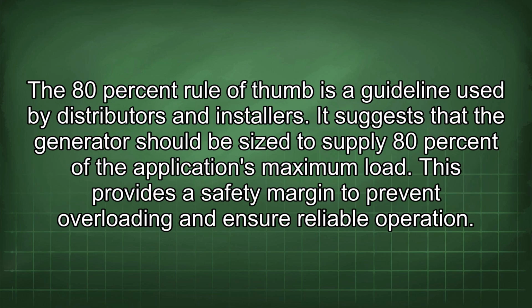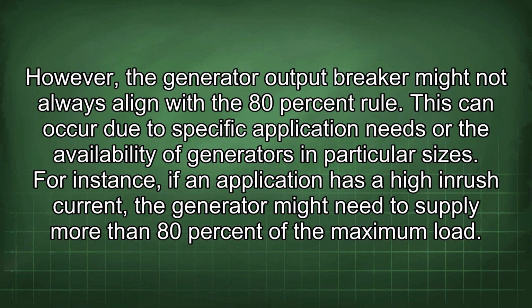The 80% rule of thumb is a guideline used by distributors and installers. It suggests that the generator should be sized to supply 80% of the application's maximum load. This provides a safety margin to prevent overloading and ensure reliable operation. However, the generator output breaker might not always align with the 80% rule. This can occur due to specific application needs or the availability of generators in particular sizes.